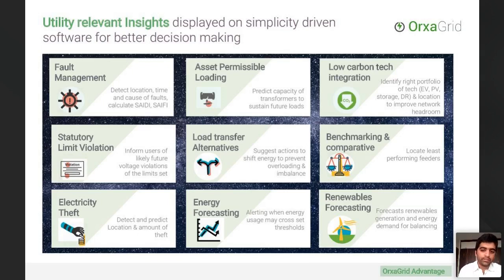Moving on to asset permissible loading. This is a feature we developed specifically for power transformers, looking at current consumption and loading, predicting future loading, looking at current temperatures, and then predicting whether the future load will be sustained by the transformer, or whether it will go into an overloaded condition to satisfy peak demand increases.